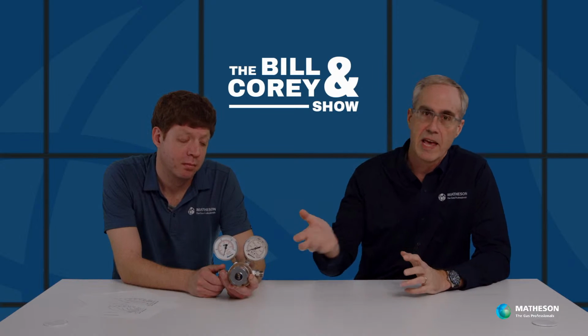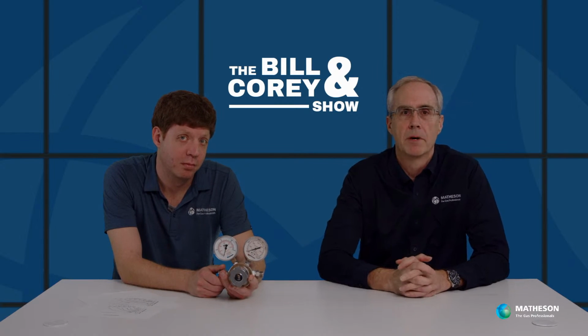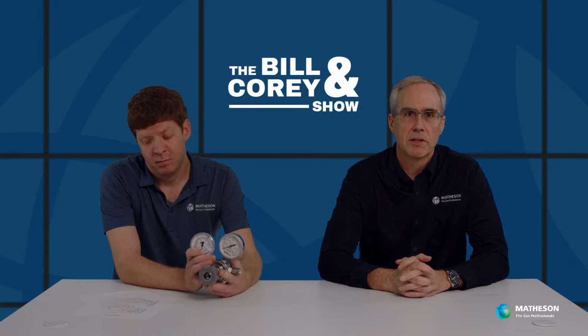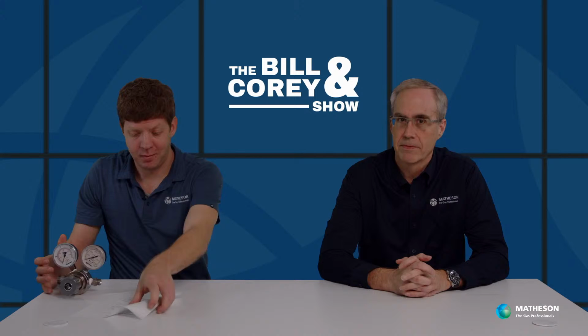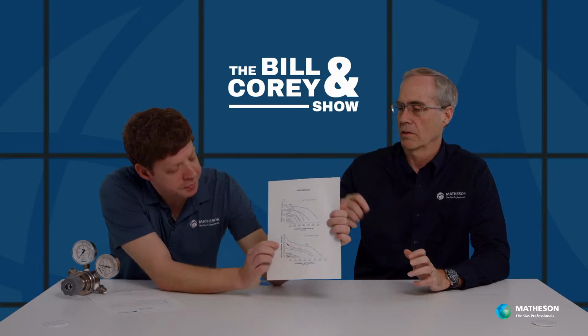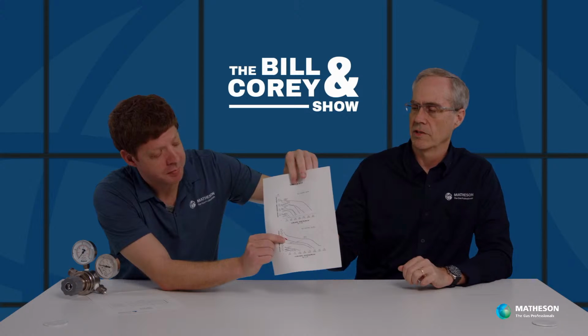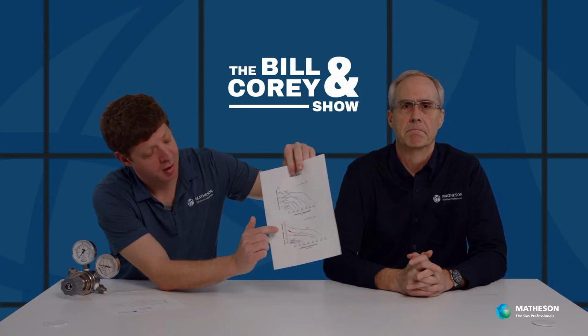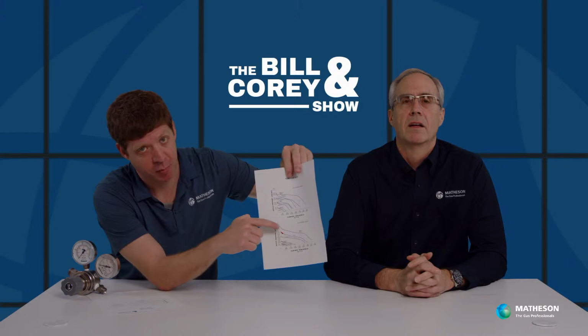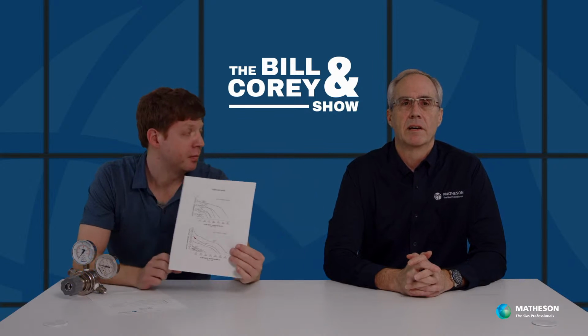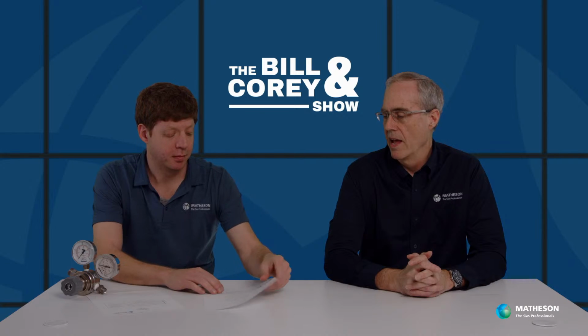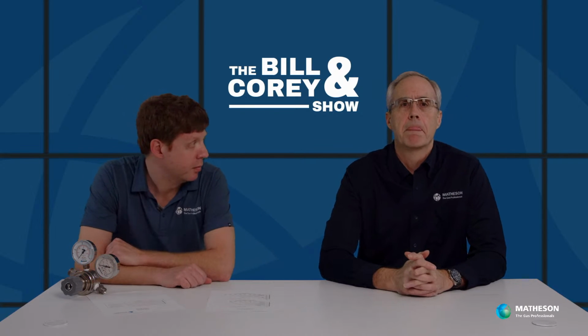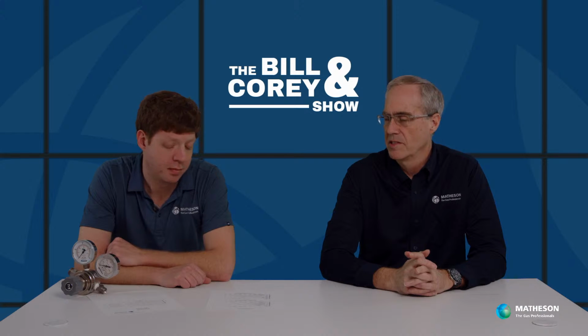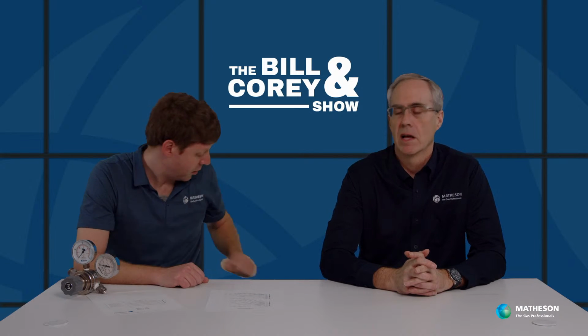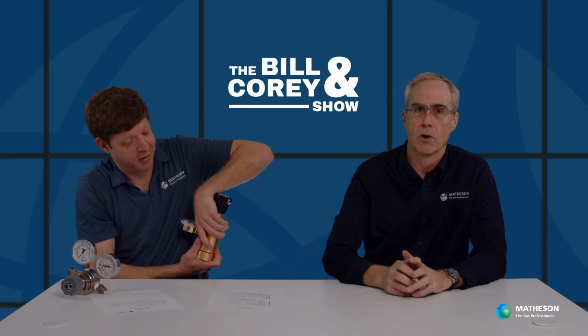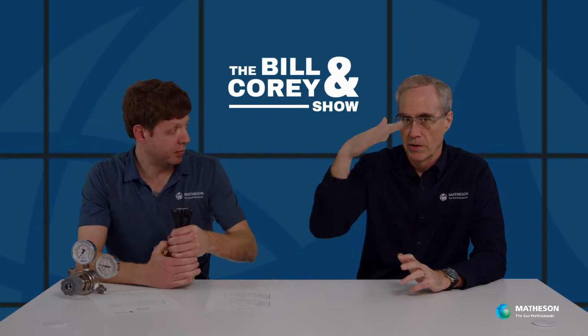And this can easily handle the flow rate that they want, but the problem is they looked at the flow curve and they saw that they were on the left-hand side of the flow curve, the lower part marked in red. So this is the flow curve. As you can see, as the flow changes, it affects the pressure. The slope is pretty steep on that end, and it levels off later on. They wanted to keep a stable outlet pressure, and this wasn't doing it for them because a small change of flow causes a big drop.